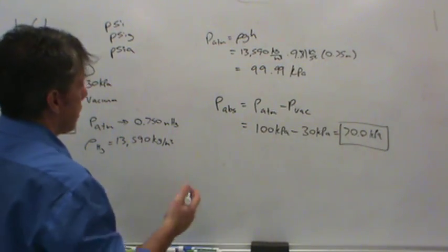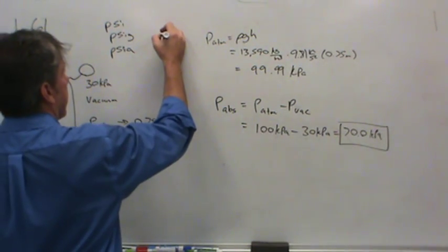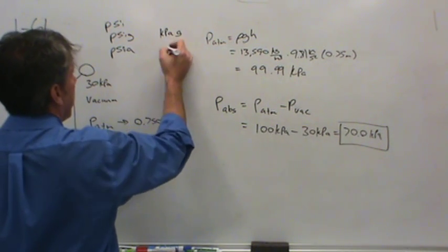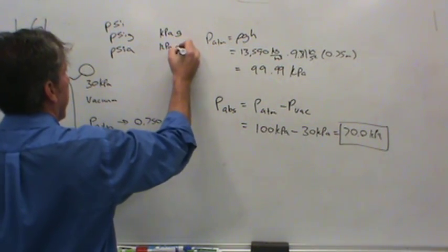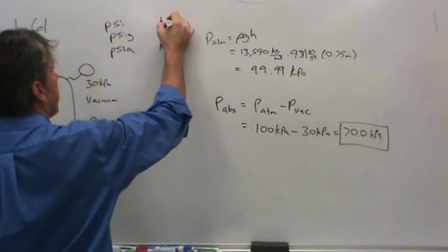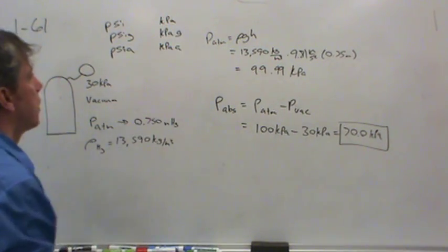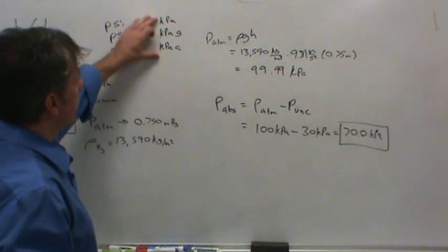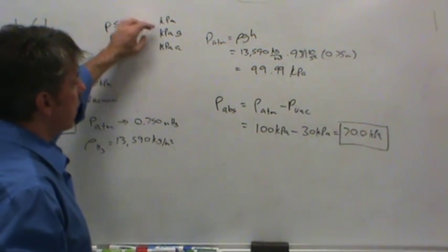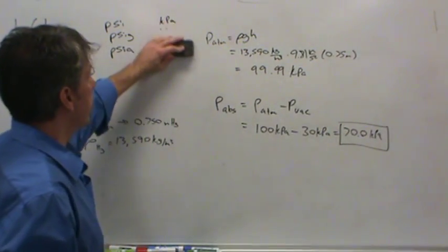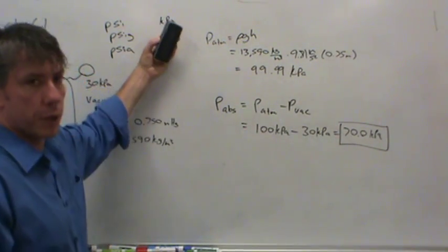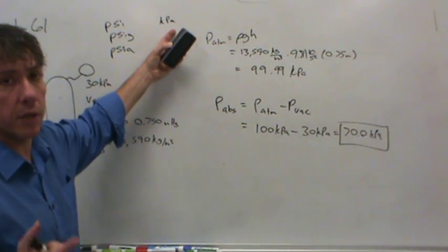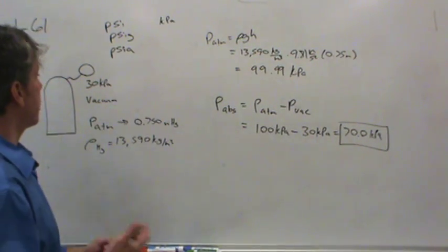But in SI, you've got kilopascals, and a kPa-G or kPa-A versus a kPa just seems difficult or useless, and so nobody really uses this. Everyone uses kilopascals. So in the SI units, you have to be really careful about whether the pressure measurement you've been given is absolute, is it gauge, is it vacuum, what is it exactly? That has to be described.